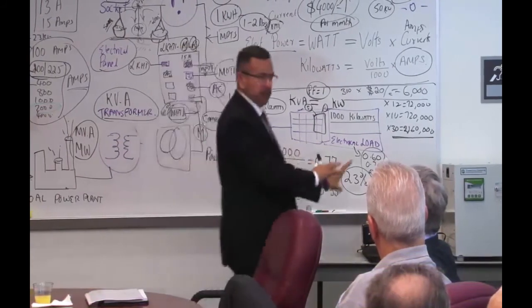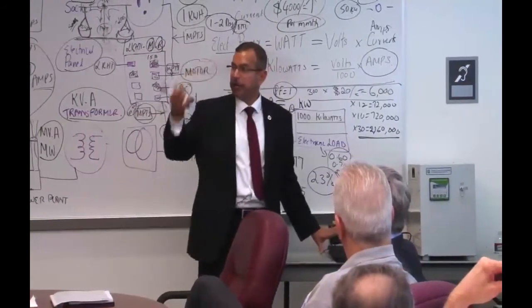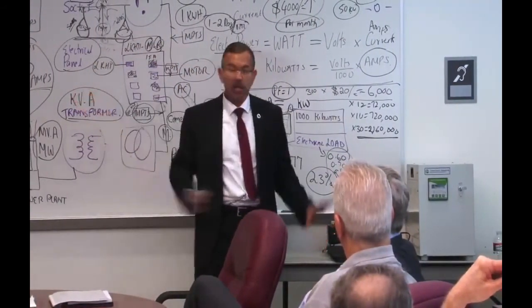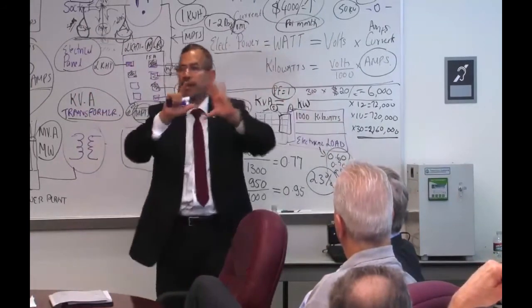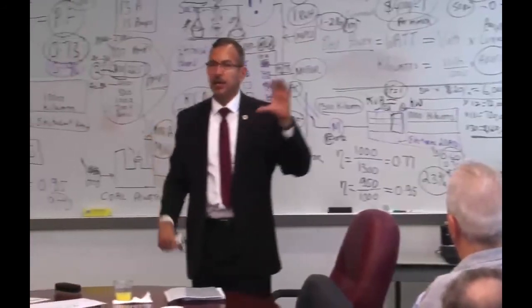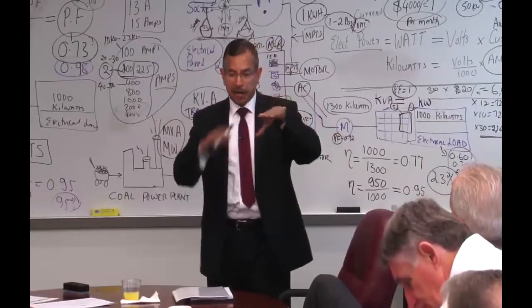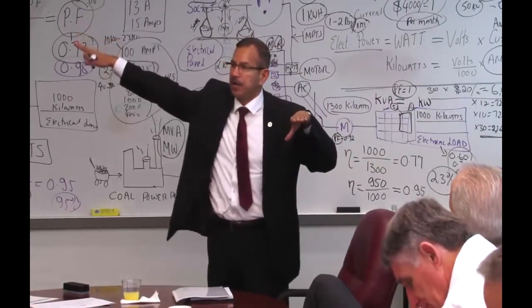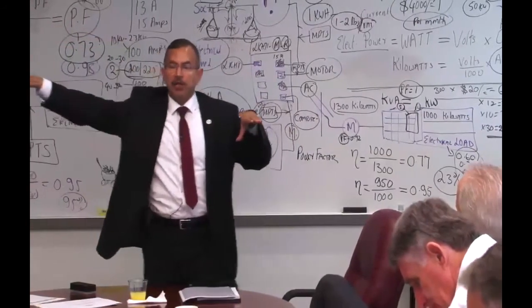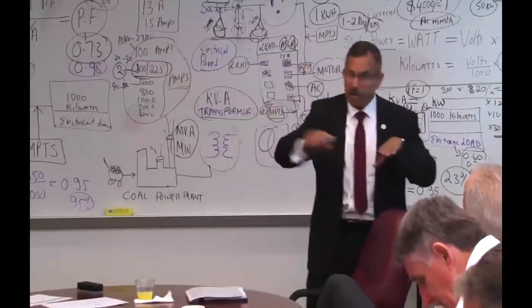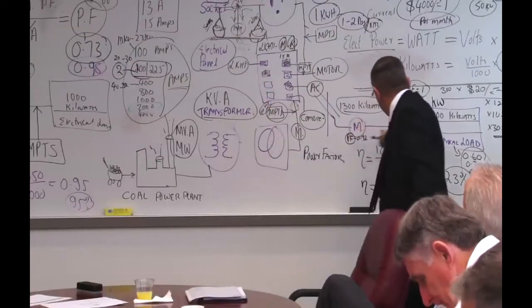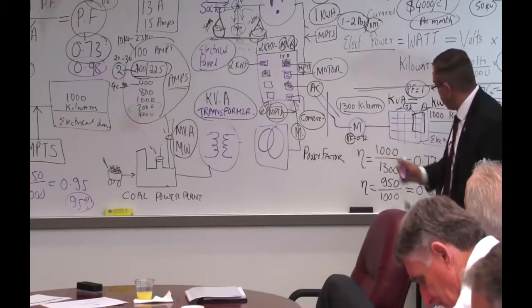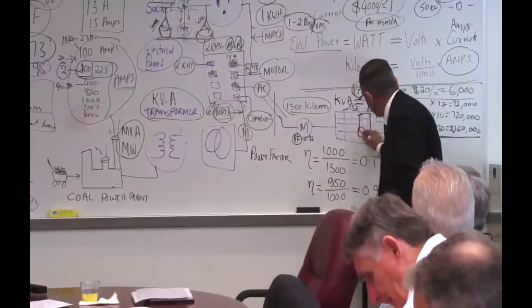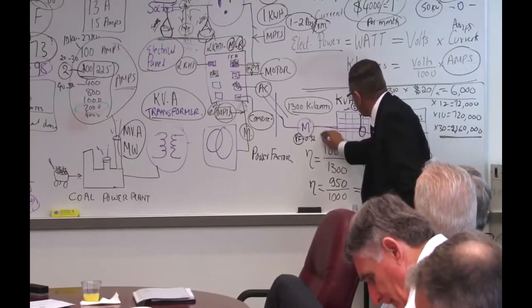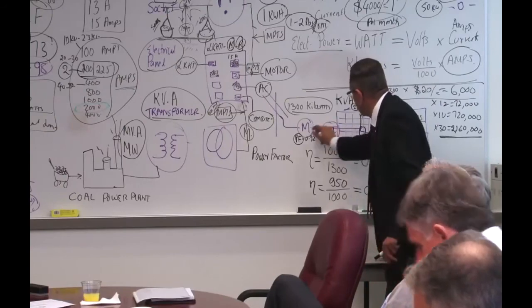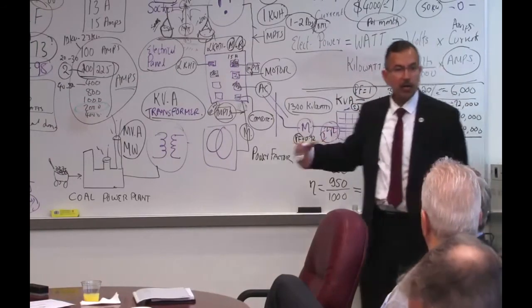Closer to the load provides you bigger benefits and better savings. Go downstream, because the solution was designed to protect equipment and reduce the current in the entire network. If you go upstream, you are not getting the benefit of lower currents being drawn from the meter all the way to the rest of the building. If the unit is farther away from the meter, you have line losses, I squared R, for the entire distance and all the panels.